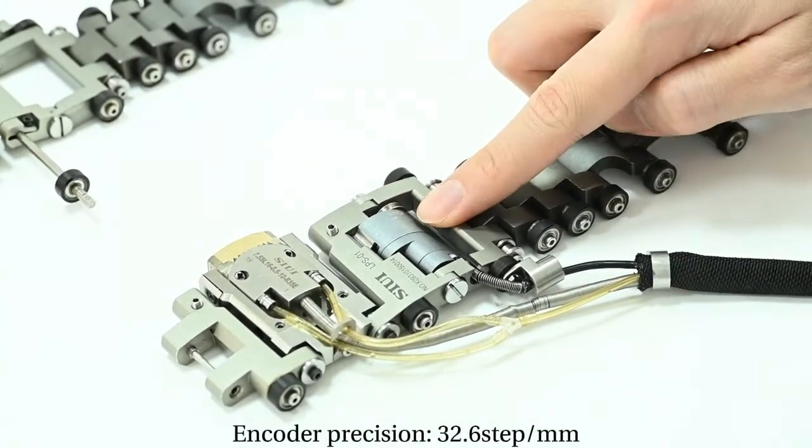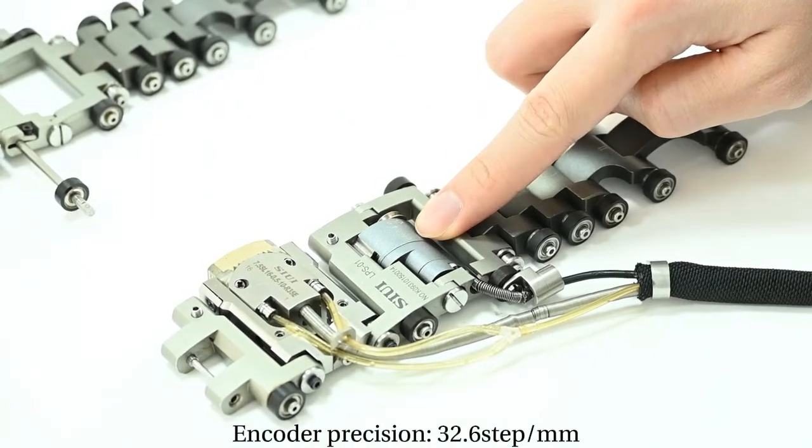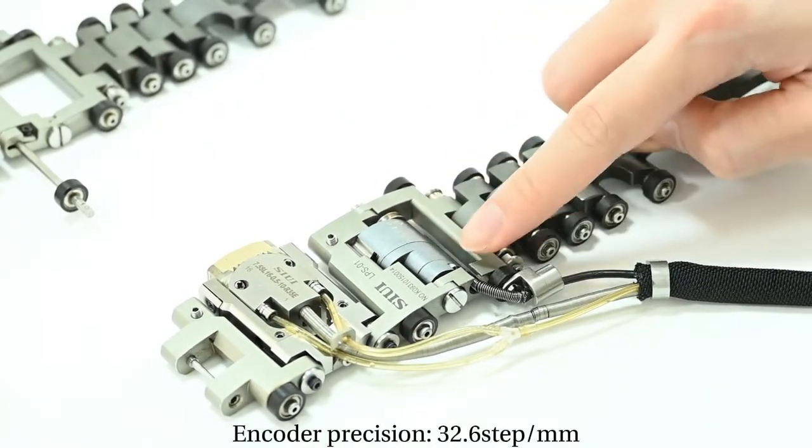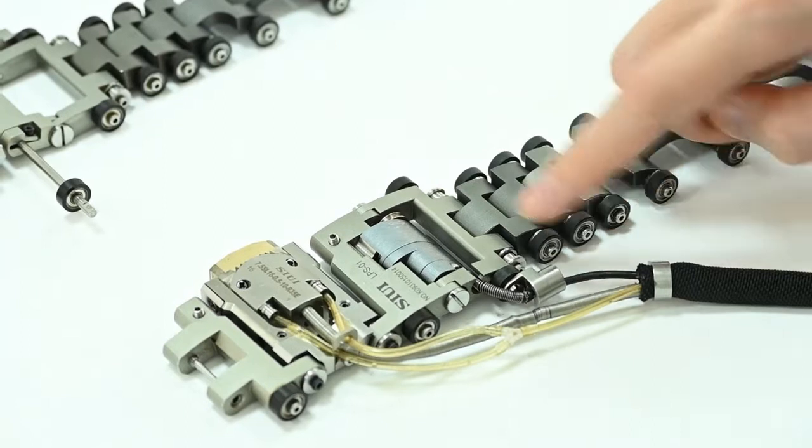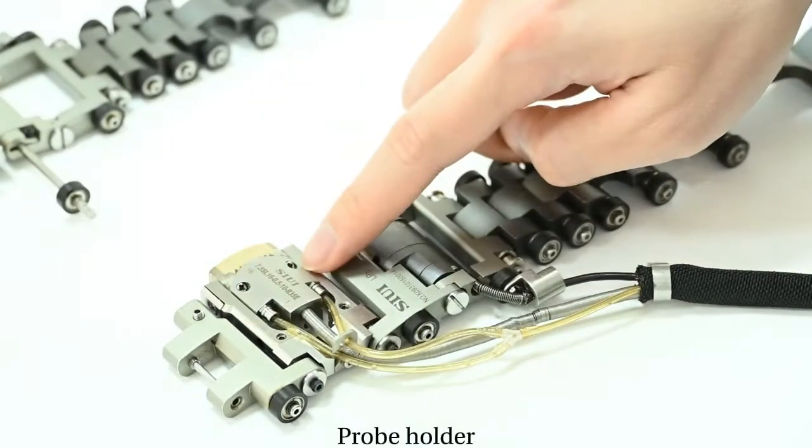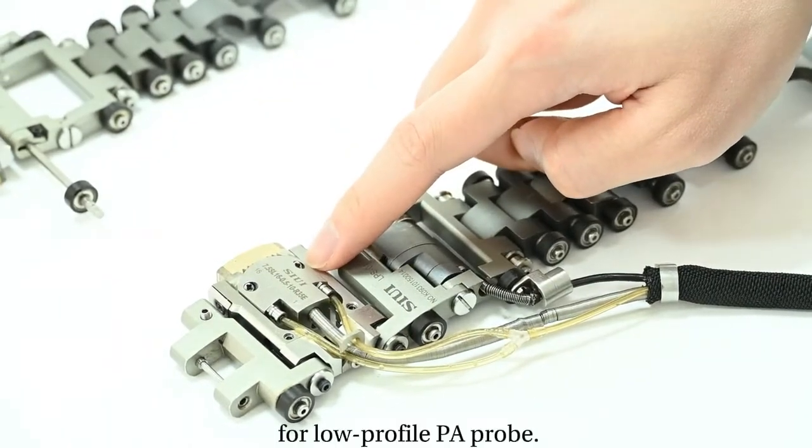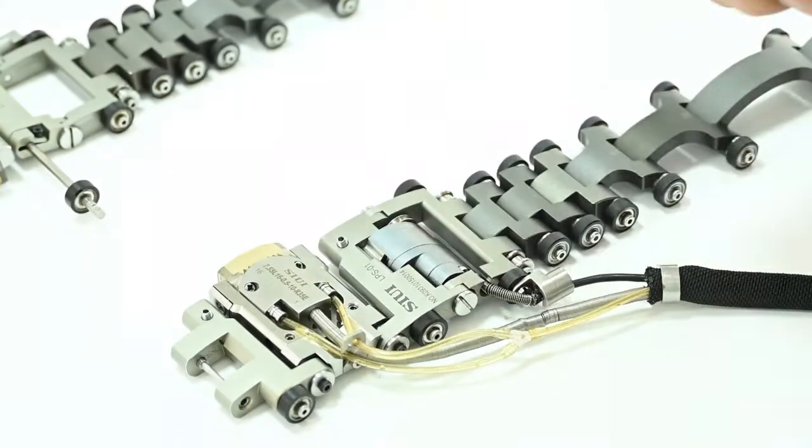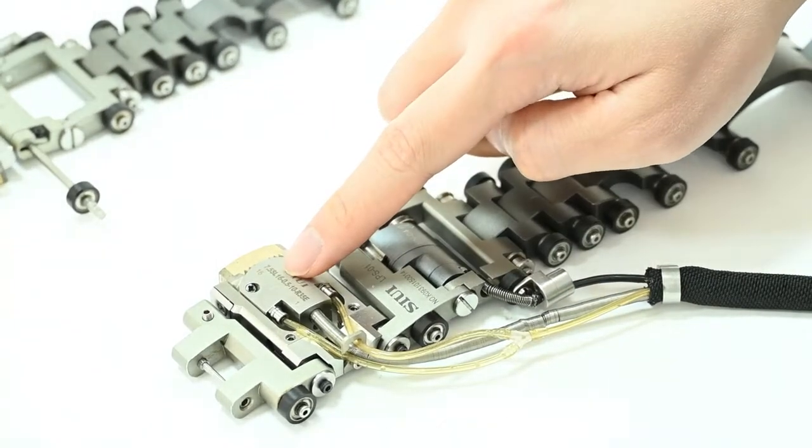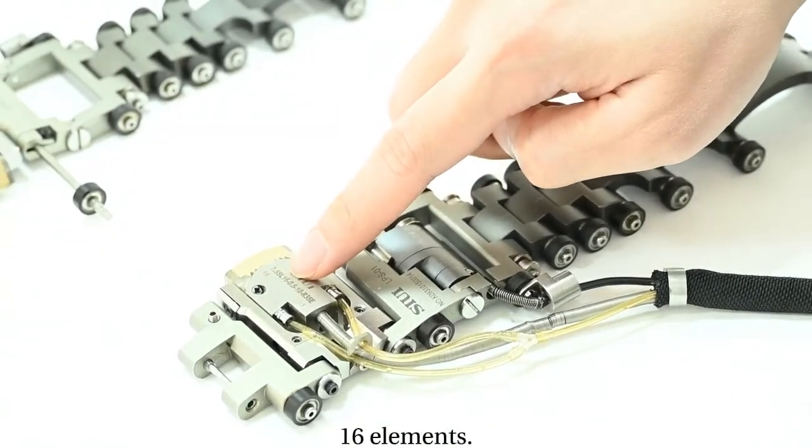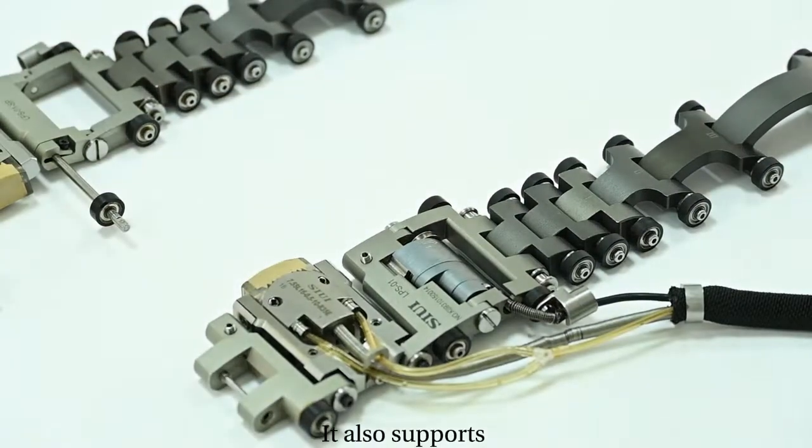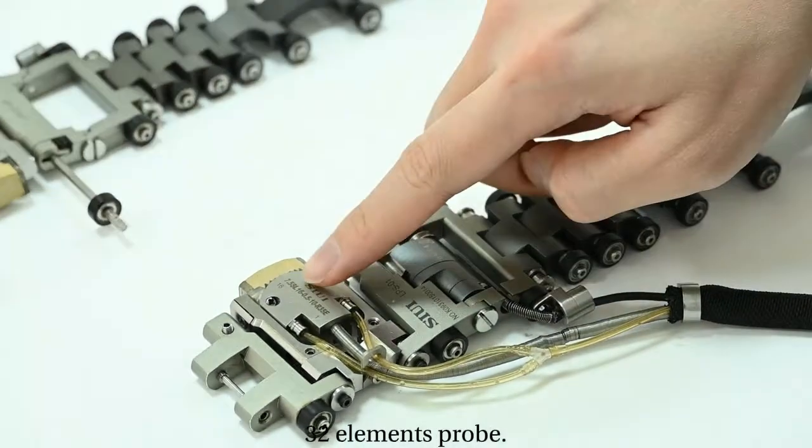Encoder with precision 32.6 steps per millimeter. Encoder cable. Probe holder for low profile phased array probe. What I show you here is a phased array probe with 16 elements. It also supports 32 element phased array probes.